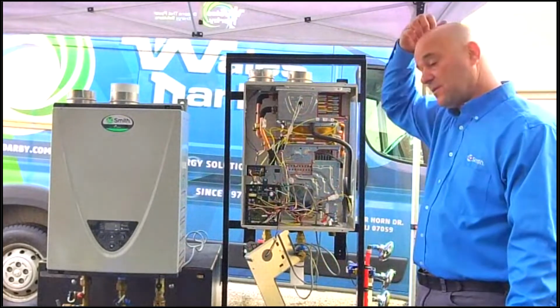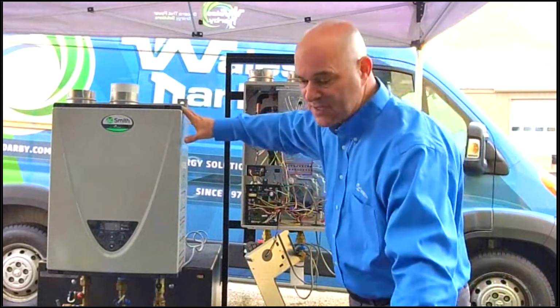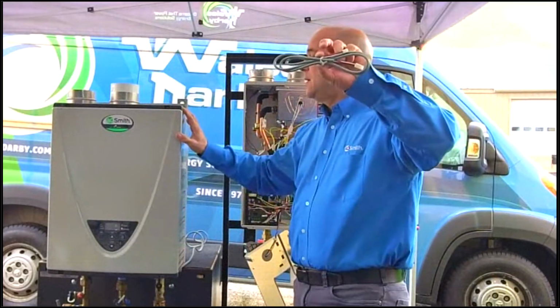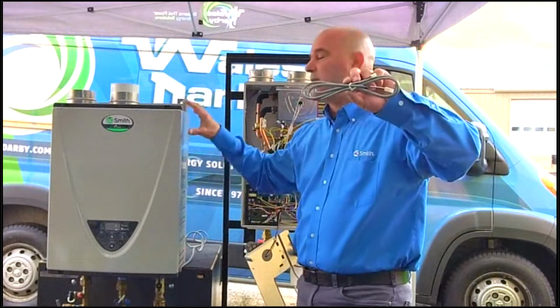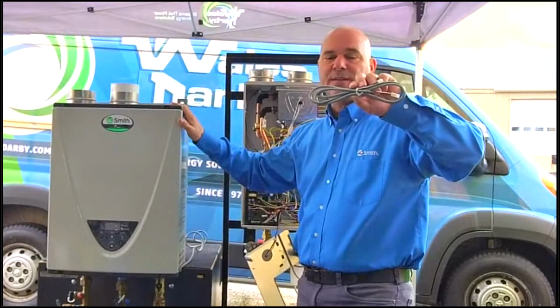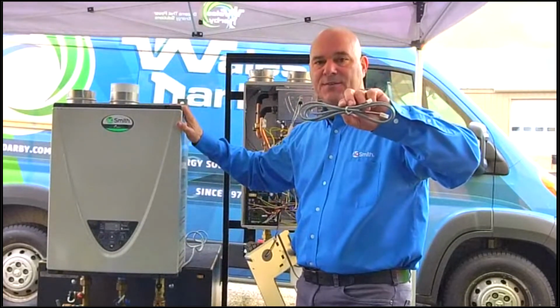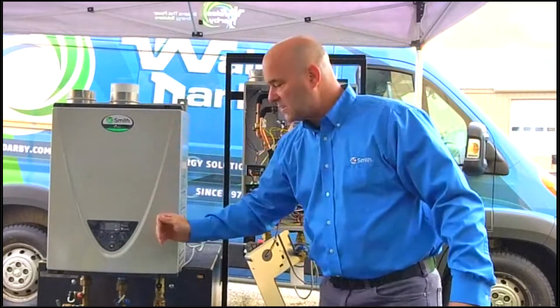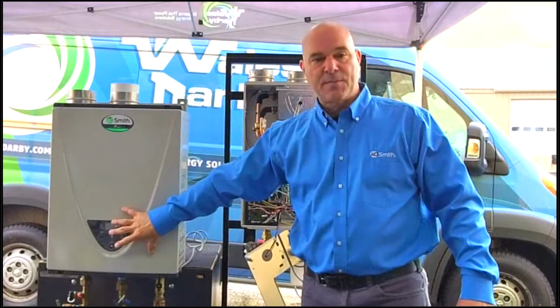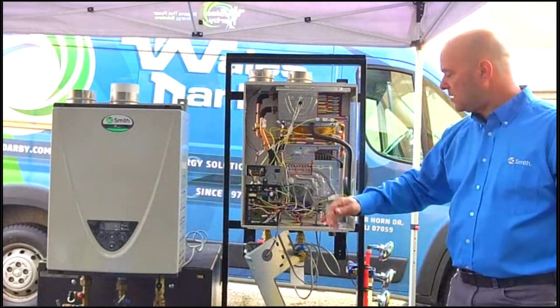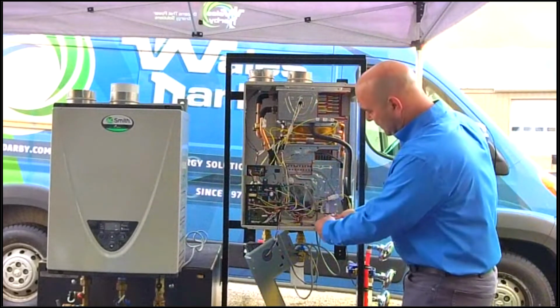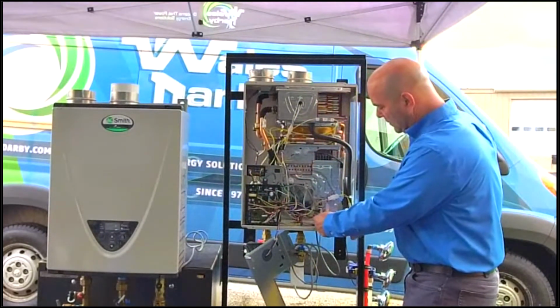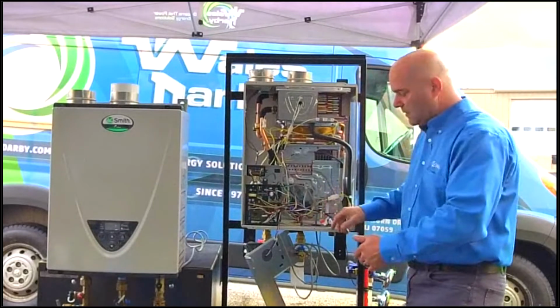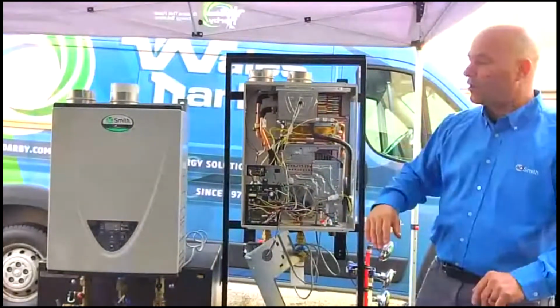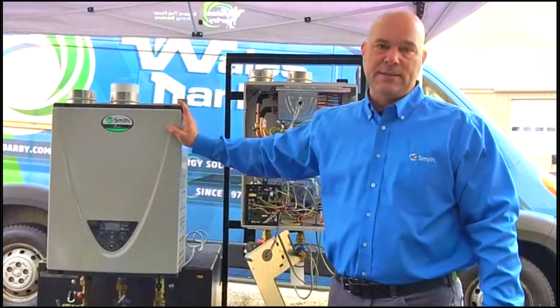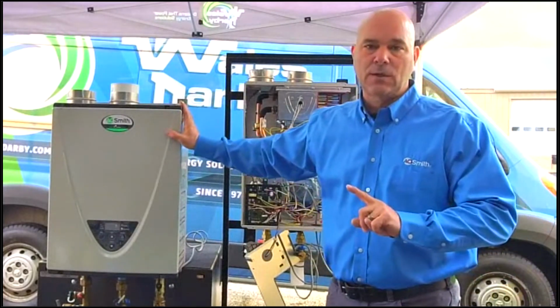Multiples, we can do multiples. Right out of the box, this comes with this gray cord. This gray cord gives you the ability to tie 4 of these units together, daisy chain them together. It becomes a parent-child type situation, and we just daisy chain them together. We tell this one it's the parent, dip switch, plugs in and out right here, parent, right? And this one will tie to the next one. Out of the next one, it'll go to the next, to the next, to the next. You get 4 of them. We can tie up to 20 of these together with one controller.